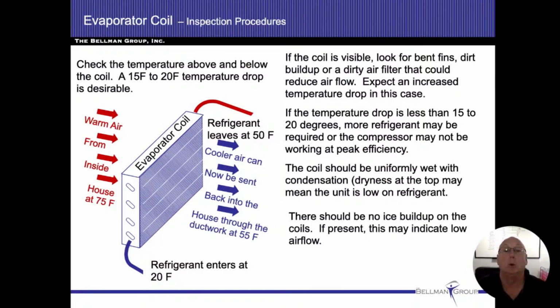All right. So going back to our list up here, if we're looking at the underside, we should see condensation flowing from it. There shouldn't be any dirt or buildup or crud on it, but you're really going to have difficulty seeing the underside of that air conditioning coil. Temperature drop is probably going to be our best test that we could do. Now, don't get me wrong. If we're at 21 degrees, that doesn't mean, danger, Will Robinson, but if we're like 25 degrees, that's a pretty big drop, way over the line. And then I would start pushing it off to an HVAC professional.